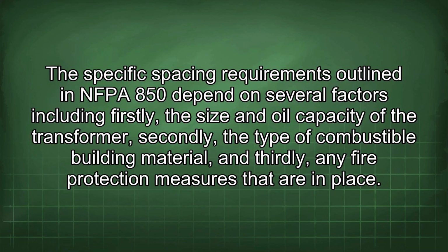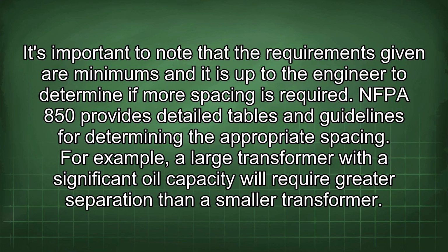The specific spacing requirements outlined in NFPA 850 depend on several factors, including firstly, the size and oil capacity of the transformer, secondly, the type of combustible building material, and thirdly, any fire protection measures that are in place. It's important to note that the requirements given are minimums, and it is up to the engineer to determine if more spacing is required. NFPA 850 provides detailed tables and guidelines for determining the appropriate spacing.